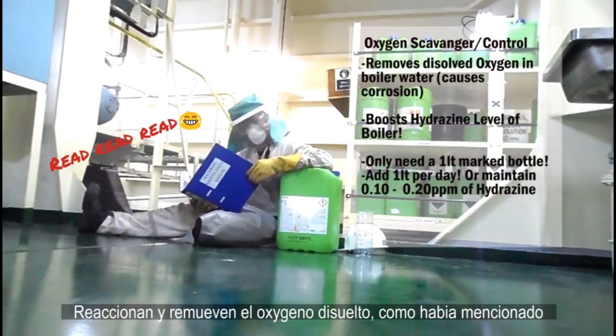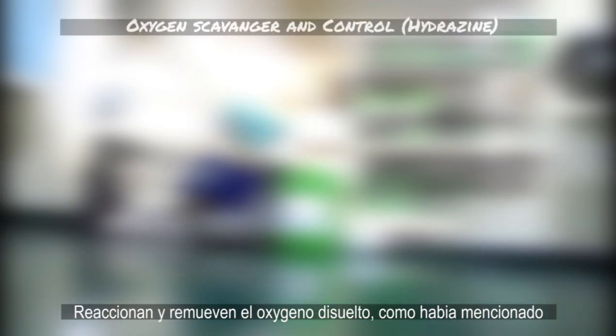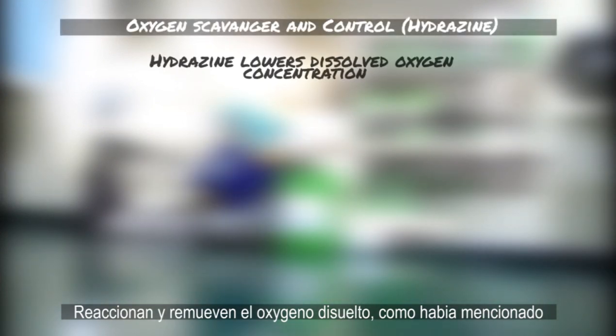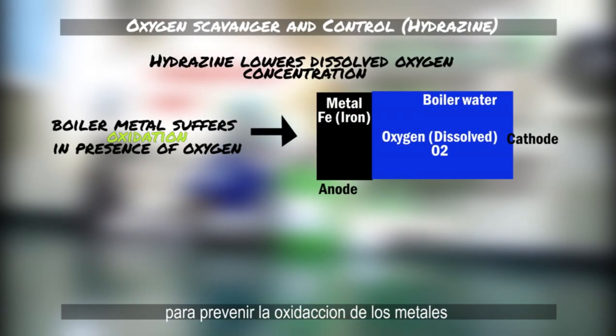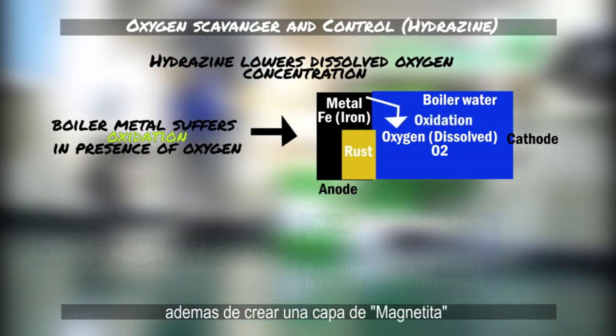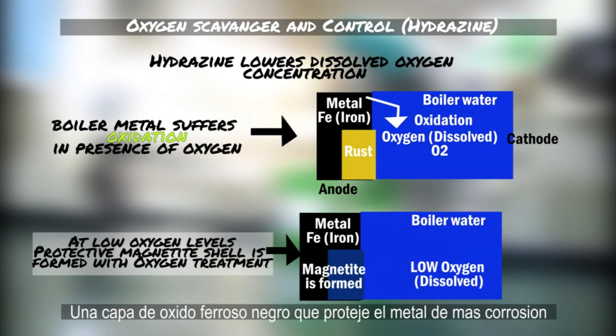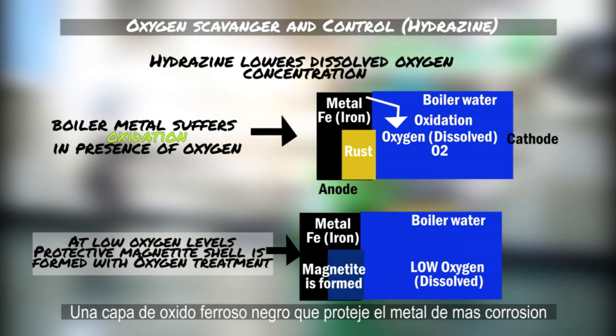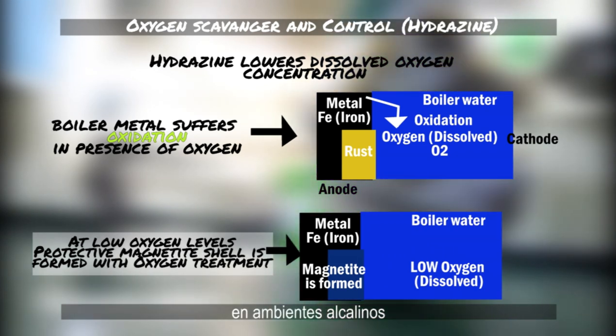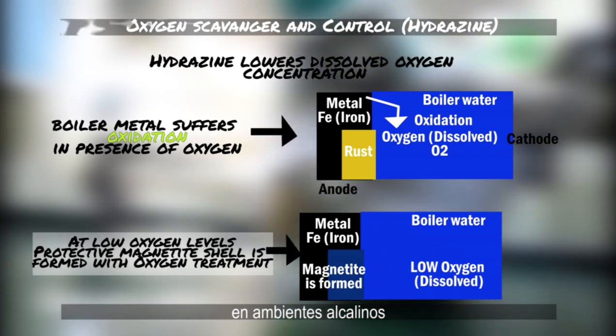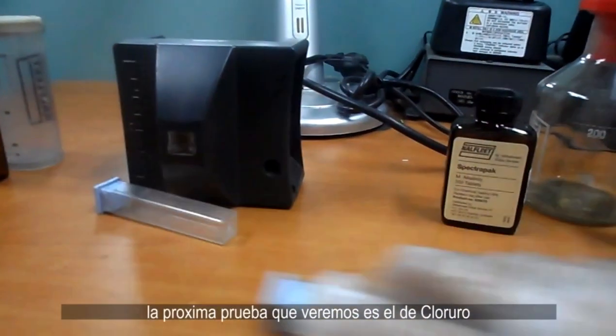To control hydrazine levels, we use Unitor's oxygen scavenger or control chemicals. They remove dissolved oxygen to prevent oxidation of the metals, and also form a coat of magnetite — a black iron oxide film that protects the metal from further corrosion in alkaline environments.